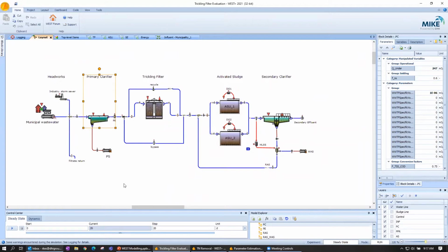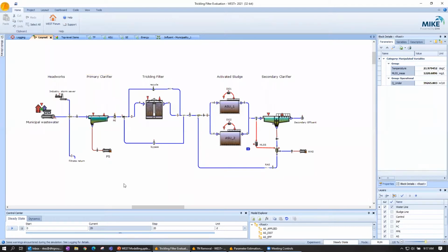But just the fact that an operator brings it up tells you that either there's a problem with skimmings, or it has an effect on the primary sludge and maybe the digester, or what they can do with that sludge, or maybe the primary clarifier operation and foaming. It's not a discussion to just table and ignore because it's not directly relevant to the model, because they are relevant to the practical application, which is why we model. We're trying to come up with some real world solutions. We're also trying to use this model in the long term for converting this into an automated model and having a digital twin online or online controls.